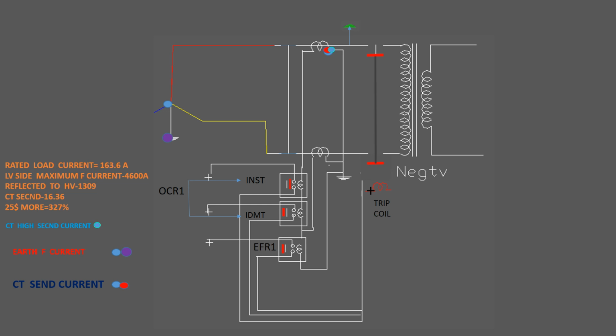Friends, as there are two CTs in the red phase and yellow phase, except for an earth fault between the CT and the power transformer winding, in all other cases both CTs will carry the same current, meaning incoming current is equal to return current in the primary, and it will return to the source. Power supply is taken from the grid through the red phase, then it will return through the yellow phase, but both CTs will carry the same current.